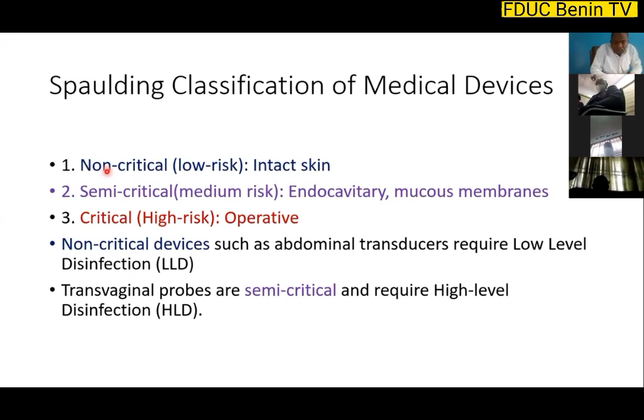For the abdominal probe, the first step is cleaning, and the second step is low-level disinfection after each use, and we'll be fine to start scanning the next patient. Many of us may not know that a lot of the probes are water tolerant, so it's possible to clean your probe. You can wash it with running water and soft cloths. This is fine and safe for the probe. We can also use some detergent wipes, but the detergent should not be abrasive, as these may damage the windows of the probe.